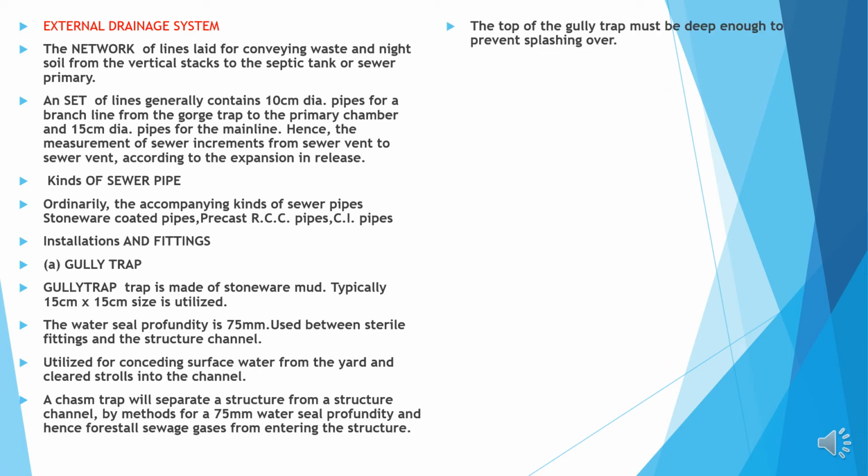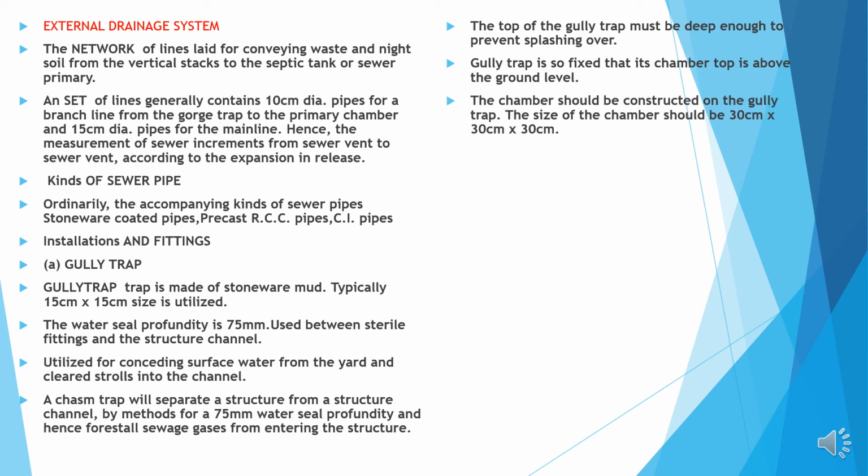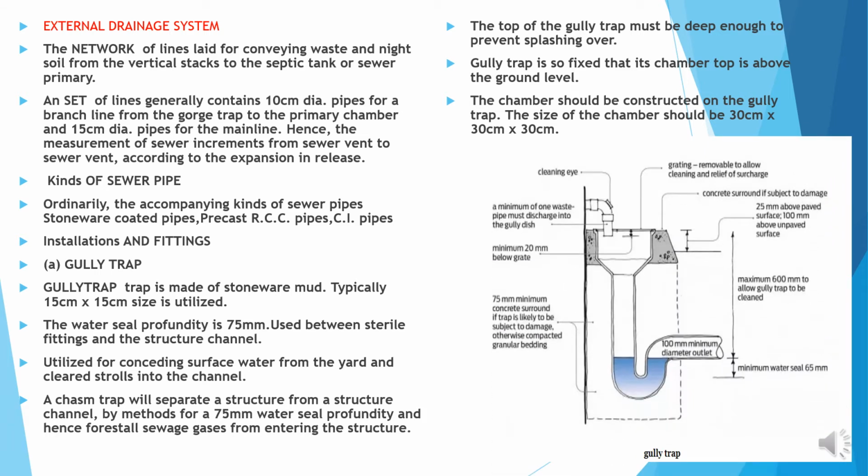The top of the gully trap must be deep enough to prevent splashing over. Gully trap is so fixed that its chamber top is above the ground level. The chamber should be constructed on the gully trap. It should be 30 centimeter by 30 centimeter. See here, the image will explain it to you.